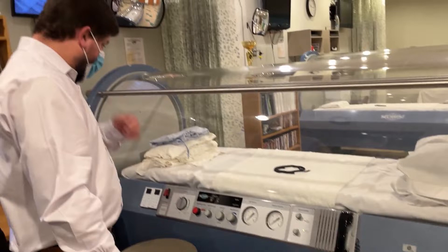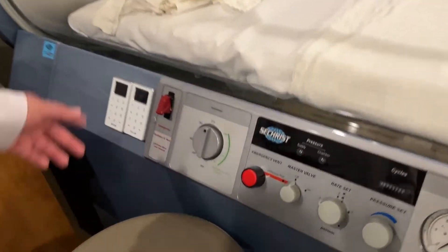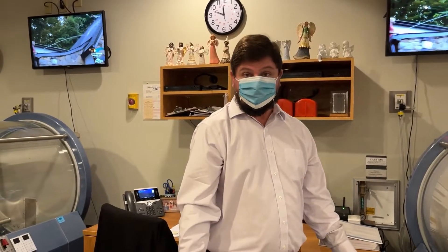We have an emergency shutdown, but really the only time you'd use it is if there were a spark or flame causing a fire in the chamber, since these are pure oxygen environments. You would emergency vent the patient in that case. However, you don't want to emergency vent a patient who is at two atmospheres of pressure, because you risk causing caisson's disease — also known as the bends — where patients can get air emboli. So short of a fire in the chamber, we are not going to trigger an emergency vent; we'll slowly bring them down to pressure.